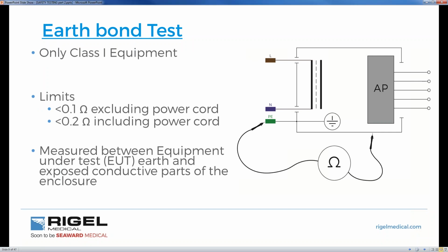Earth bond. So what are we measuring with earth bond? If this is our medical device, and these are our live conductors in and neutral, this is our protective earth. We want to make sure with the medical device, and this is our chassis of the medical device, if any conductive accessible parts have, on a class 1 appliance, because earth bond is class 1 only, or class 1 equipment only, we want to make sure that any accessible parts that are metallic and conductive have a low path of resistance to the protective earth.